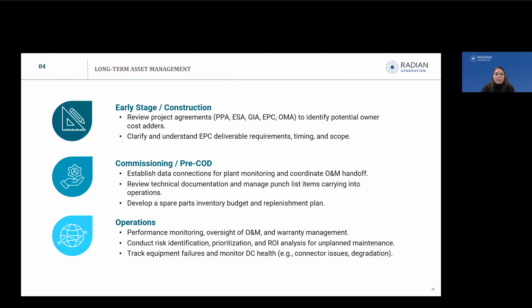In operations, asset management shifts to active oversight and helping owners make data-driven decisions that optimize their plants. For example, seeing a small persistent DC health loss issue may not be a high maintenance priority, but choosing not to prioritize it can ultimately be far more costly than even a single dramatic equipment failure at the inverter level. Performance monitoring, oversight of the O&Ms, and warranty management keeps everything on track and flags anything lagging or causing revenue losses.